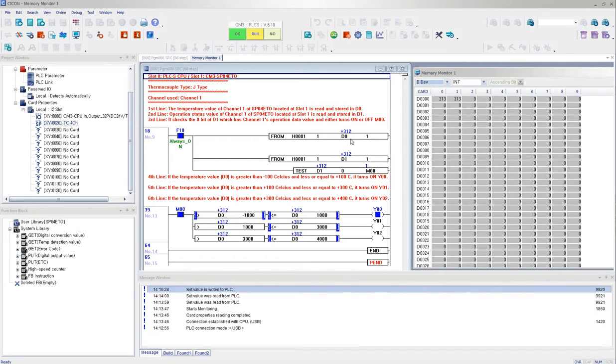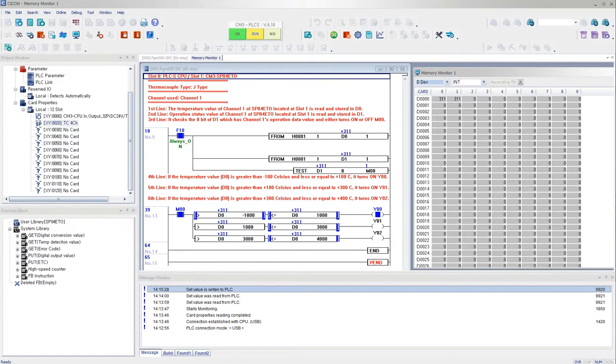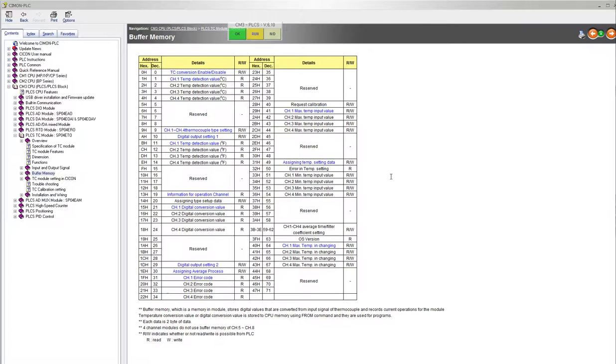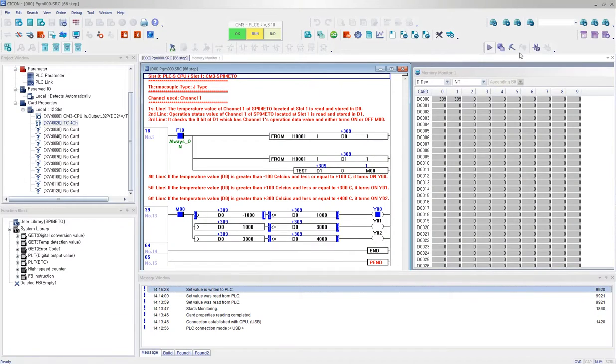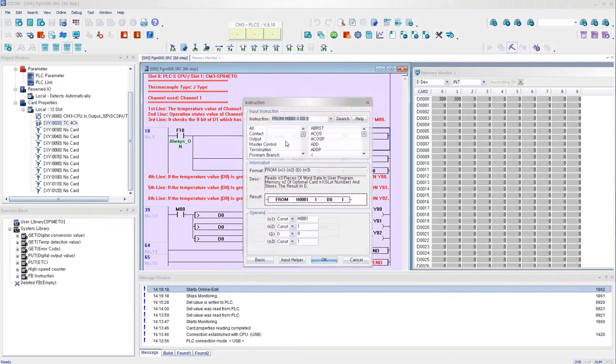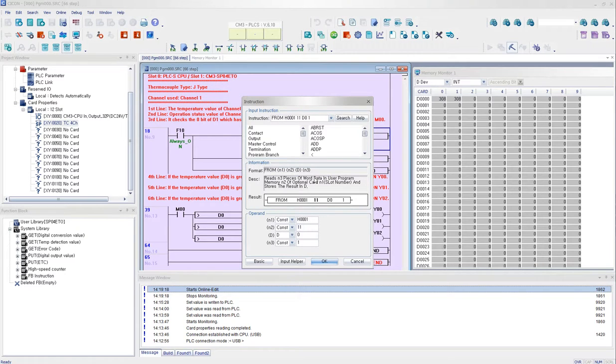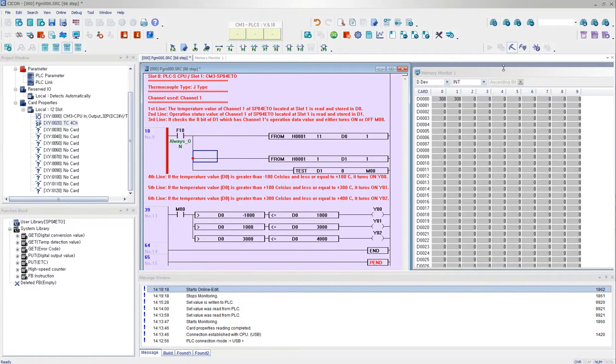So let's say right now I'm reading the channel 1 temperature value in Celsius. If you want to read it in Fahrenheit, then what you can do is refer to the help documentation. The buffer memory says it is 11 in Fahrenheit. So I go ahead and then I click on online edit. I double click the FROM command. All I need to do is to change this number to 11, which will bring the data and display it in Fahrenheit.